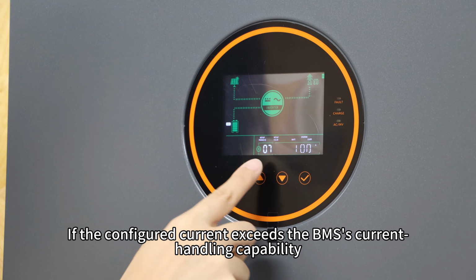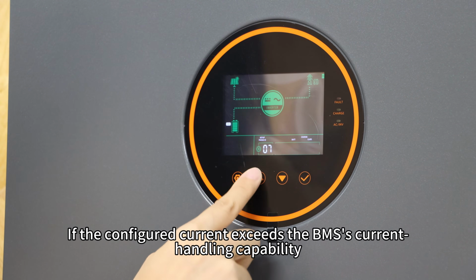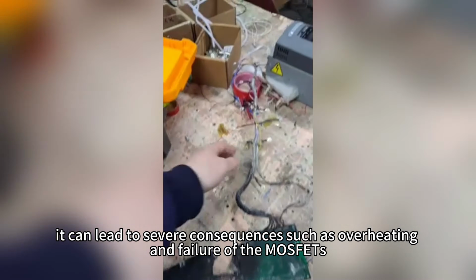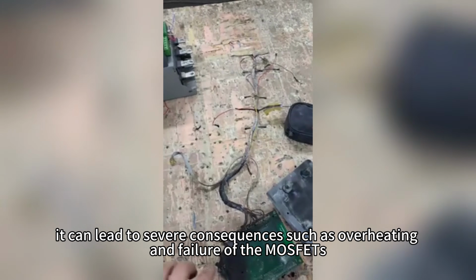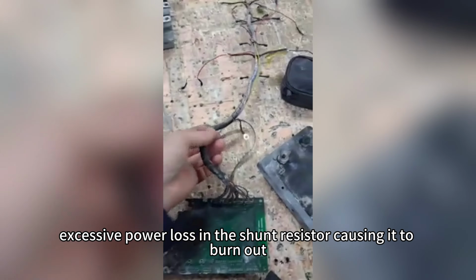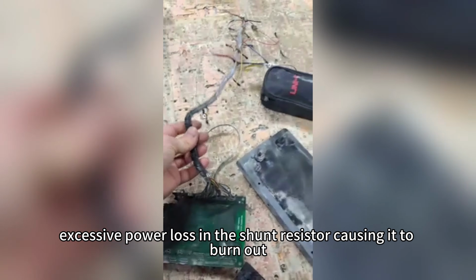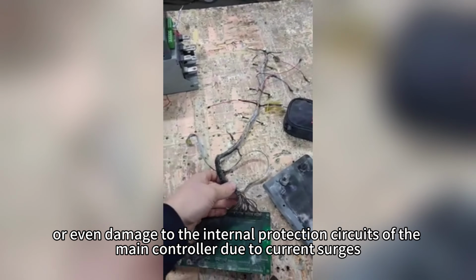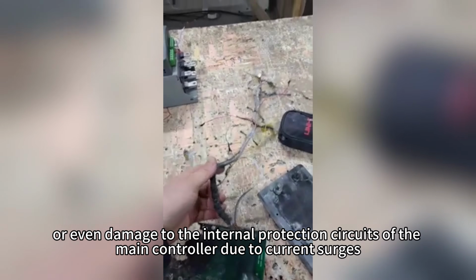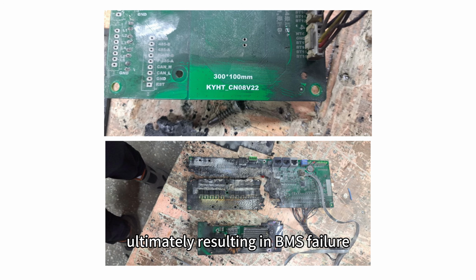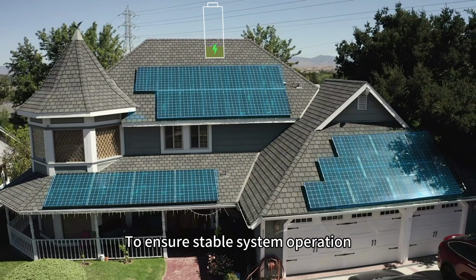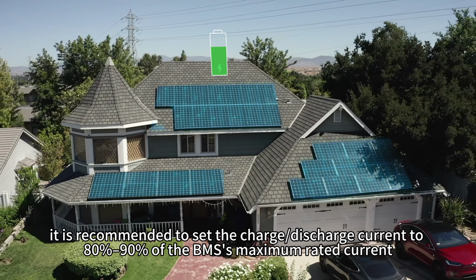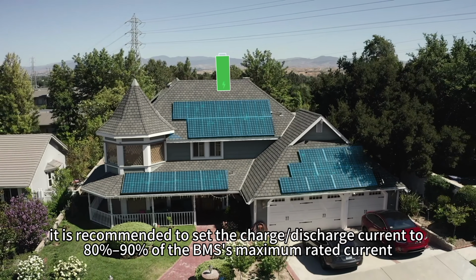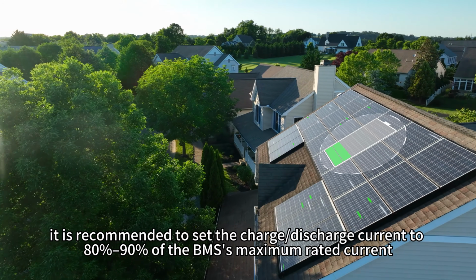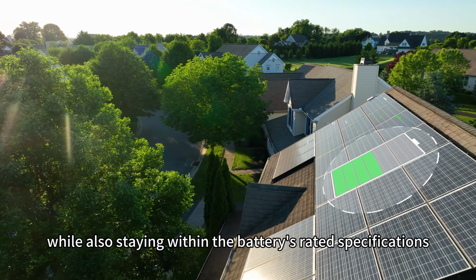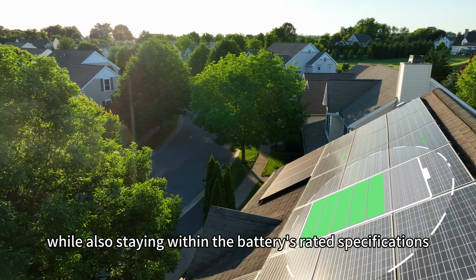If the configured current exceeds the BMS's current handling capability, it can lead to several consequences such as overheating and failure of MOSFETs, excessive power loss in the shunt resistor causing it to burn out, or even damage to the internal protection circuits of the main controller due to current surges, ultimately resulting in BMS failure. To ensure stable system operation, it is recommended to set the charge or discharge current to 80% to 90% of the BMS's maximum rated current, while also staying within the battery's rated specifications.